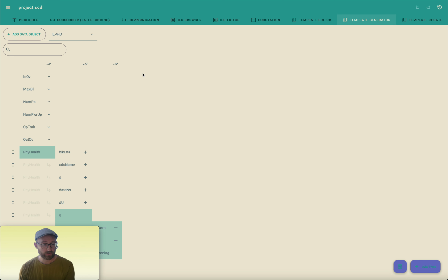That plugin allows you to create new logical node types and add them to your data type template section. The plugin is based on so-called NSD files, namespace description files. Those are XML files, machine-readable components shipped with the standard that you can download from the official homepage of the IEC 61850. These files contain the tables that you can see in parts 7-4 and 7-3, some enumerations and other structured types, also from 8-1 and 7-2.